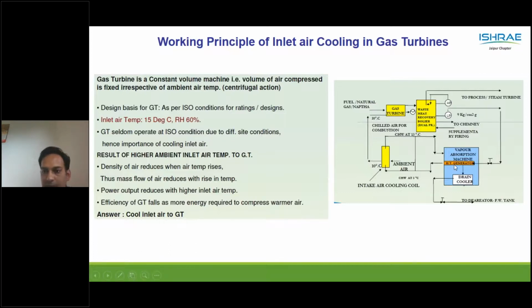Hence the solution is cooling of the inlet air. Vapor absorption machines, as shown in the schematic diagram, produce chilled water which goes to the cooling coil fitted on the air filter of the gas turbine. The air that goes to the gas turbine is chilled to 10 degrees and it produces to its maximum output capacity. There is a waste heat recovery boiler which also produces steam, through which the vapor absorption machine runs.